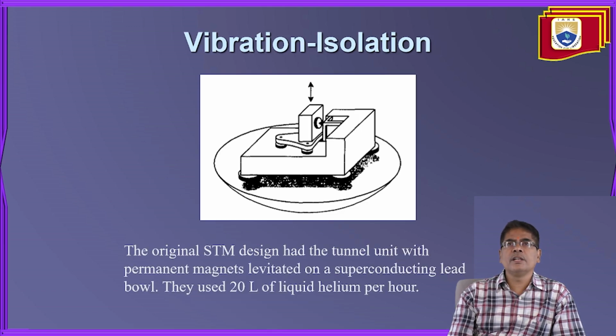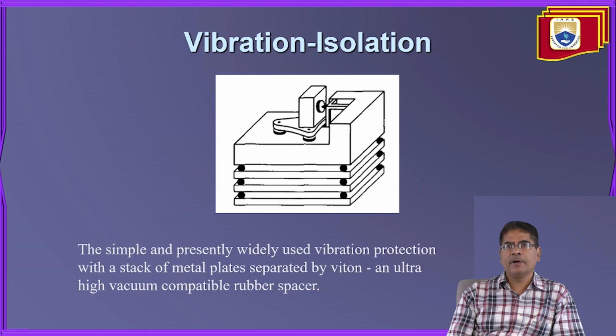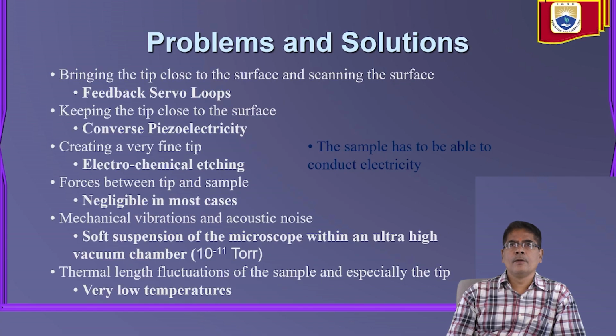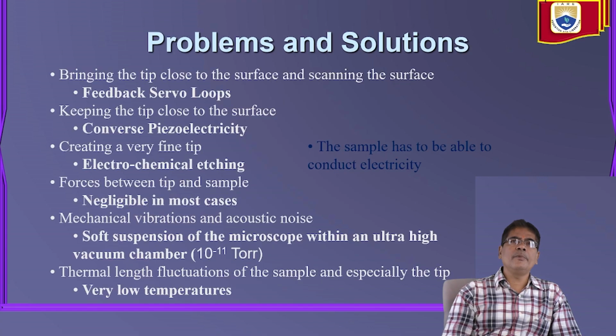So vibration isolation, right? The original STM designs have the tunnel unit with permanent magnets levitated on a superconducting lead bowl. They use around 20 liters of liquid helium per hour. Liquid helium you need to pour. So vibration protection that is simple and presently widely used is a stack of metal plates separated by Viton, an ultra high vacuum compatible rubber spacer. So these are some of the problems and solutions.